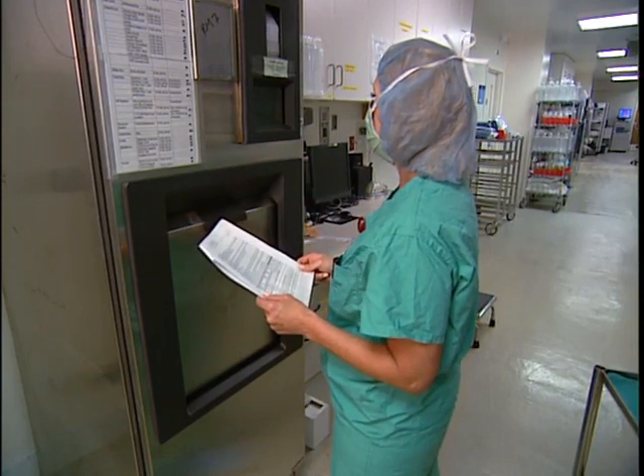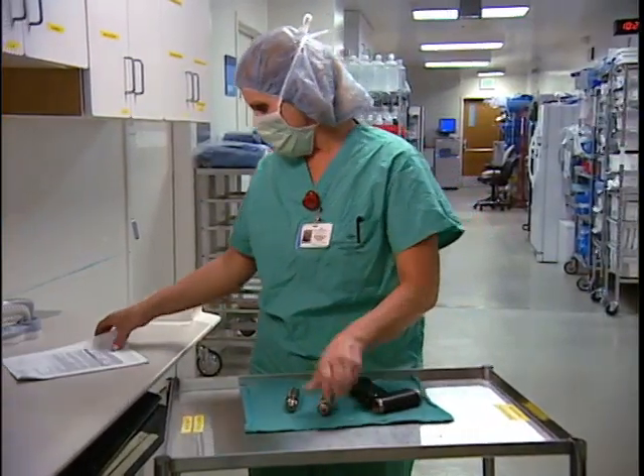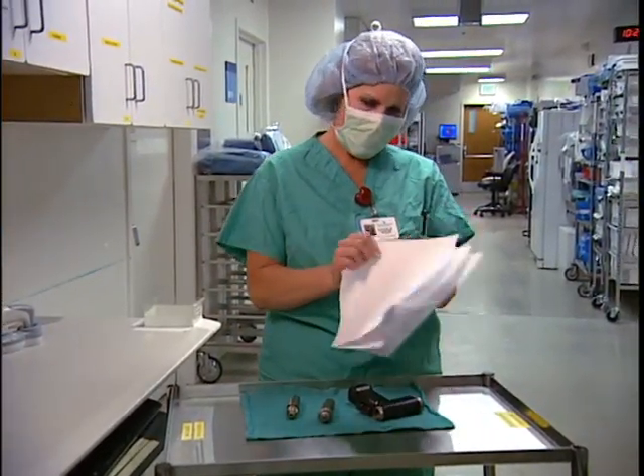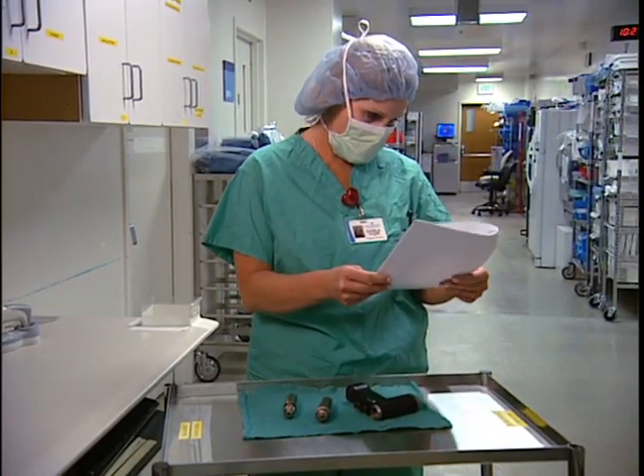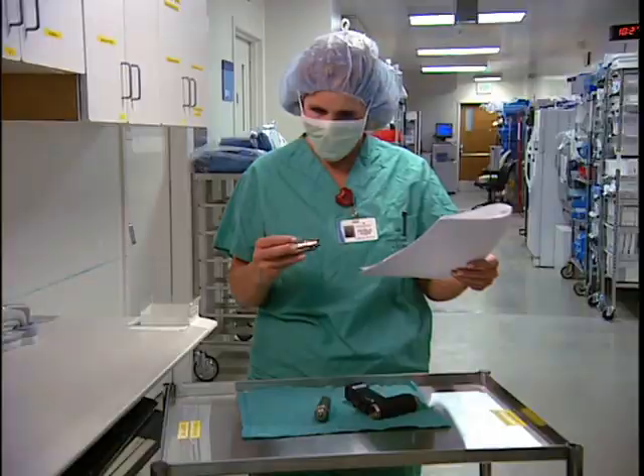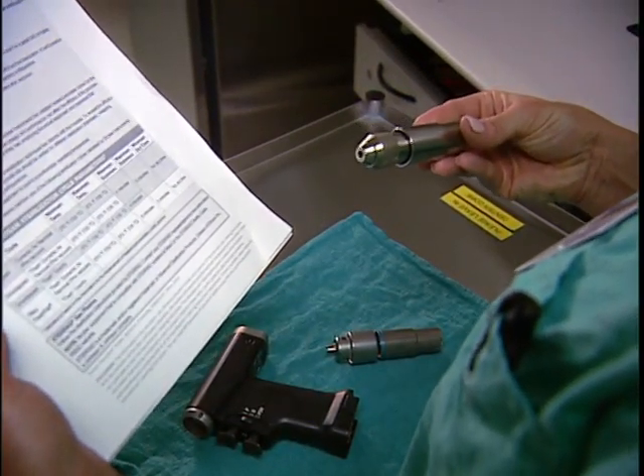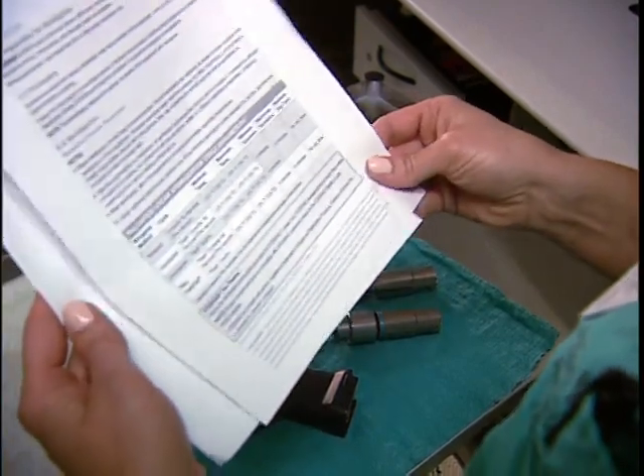On rare occasions, the manufacturer's instructions for the instrument, for the container that it's packaged in, and for the sterilizer that it will be sterilized in are not compatible, and they may say different things. When that happens, it's important to go back to the manufacturers to receive additional guidance to find out how to handle it. If you need the instrument right away, follow the instrument manufacturer's guidelines for sterilization. There are certain devices that should never receive immediate use steam sterilization. Be aware that some instruments may be terminally sterilized but are not approved for immediate use sterilization, so always check the device manufacturer's written instructions.